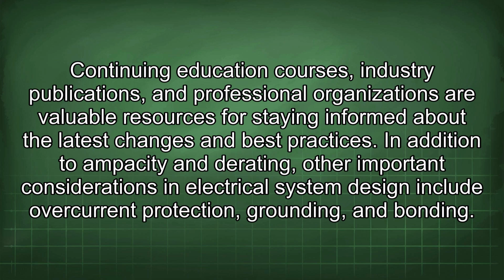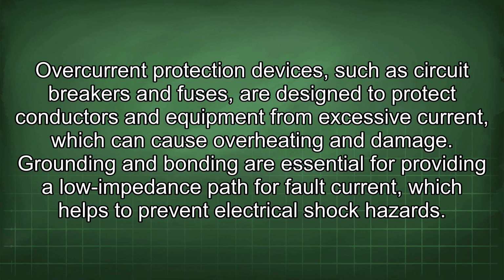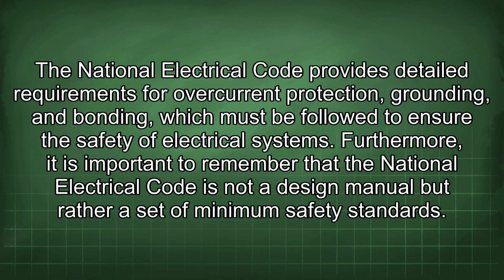In addition to ampacity and derating, other important considerations in electrical system design include overcurrent protection, grounding, and bonding. Overcurrent protection devices, such as circuit breakers and fuses, are designed to protect conductors and equipment from excessive current, which can cause overheating and damage. Grounding and bonding are essential for providing a low impedance path for fault current, which helps to prevent electrical shock hazards. The National Electrical Code provides detailed requirements for overcurrent protection, grounding, and bonding, which must be followed to ensure the safety of electrical systems.